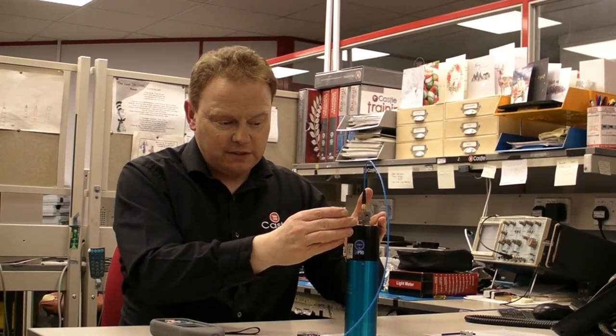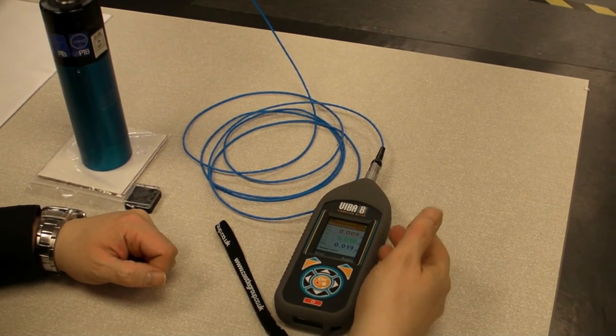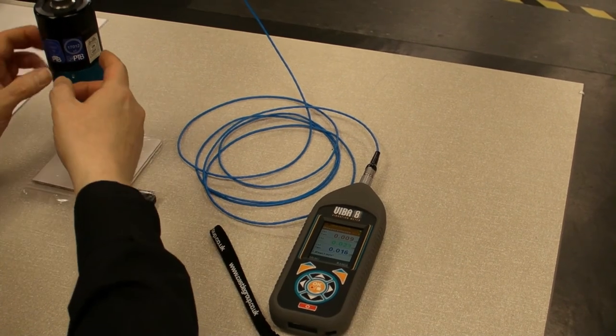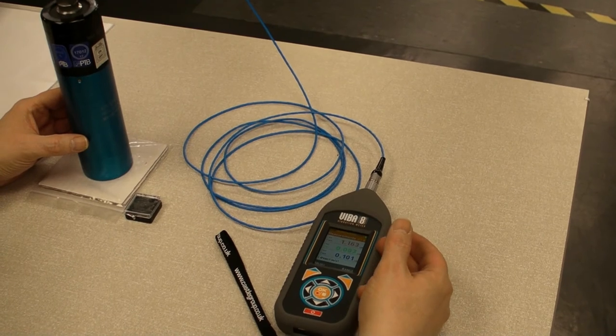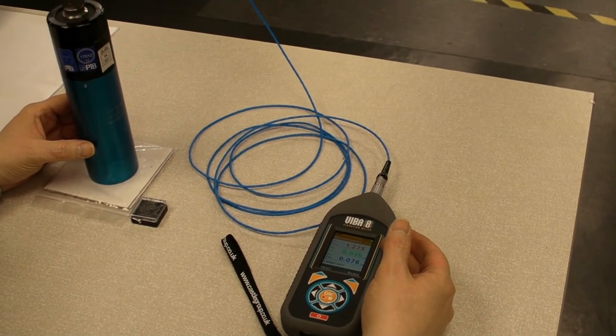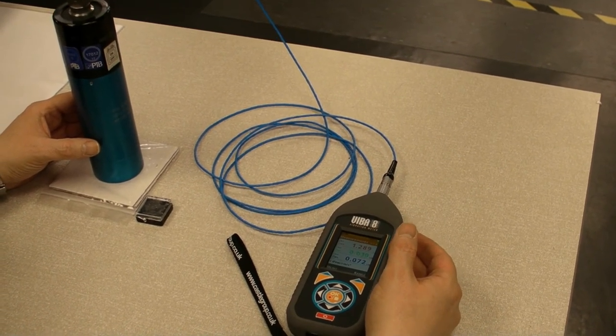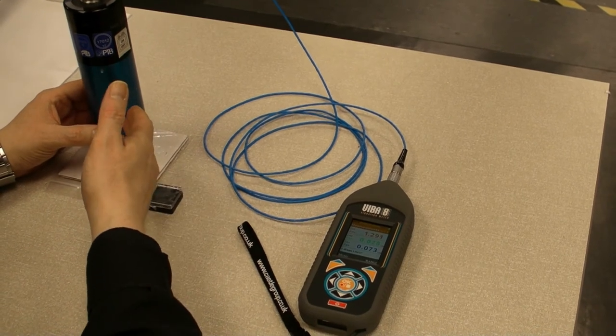So the accelerometer is now attached to the shaker and now we set the instrument into the calibration mode.